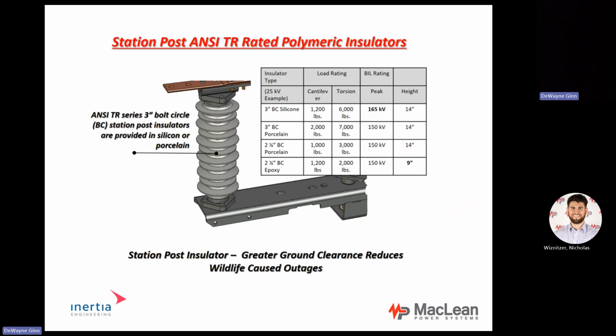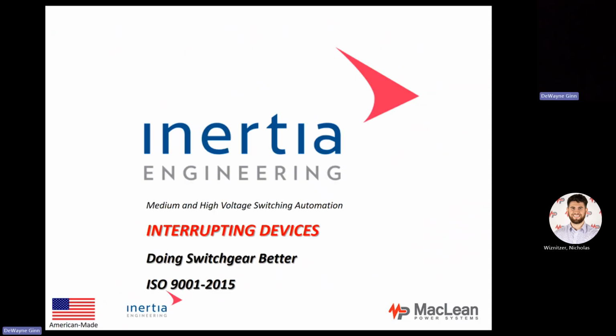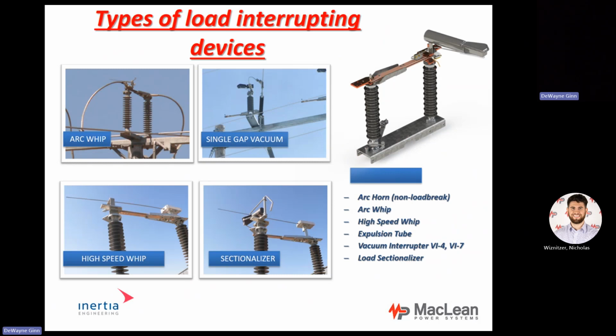Again, station post insulators, primarily we've always used MacLean as well. Interrupting devices, we talked a little bit about those earlier, but we make all our interrupting devices in-house: our arcing horns, our arc whips, high-speed whips, expulsion tubes, vacuum interrupters, which is a V4 and V7, and our sectionalizer switch, all in-house. So an arc whip is good for a 1/2 amp per mile, up to 20 miles for 10 amps. With a high speed, you could go up to 20 amps, which will allow you probably 40 miles.